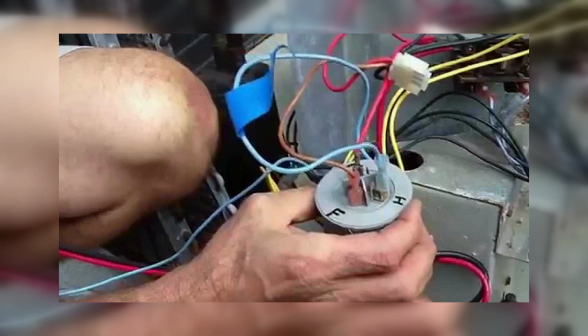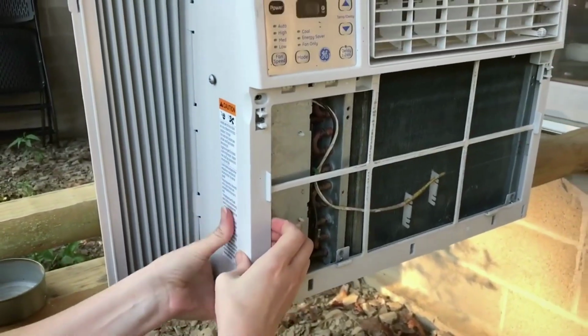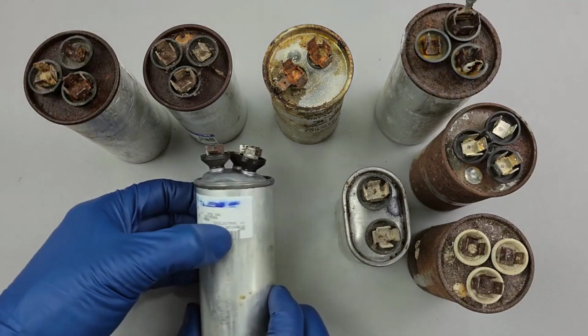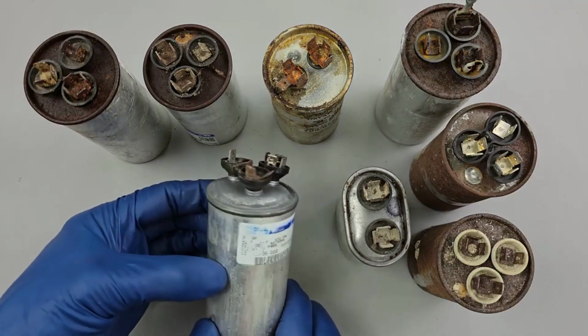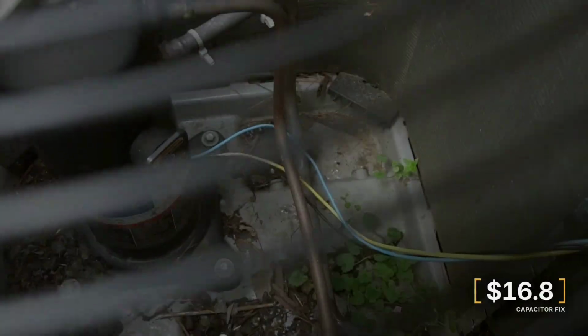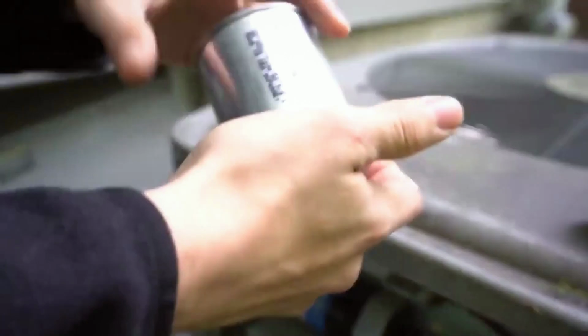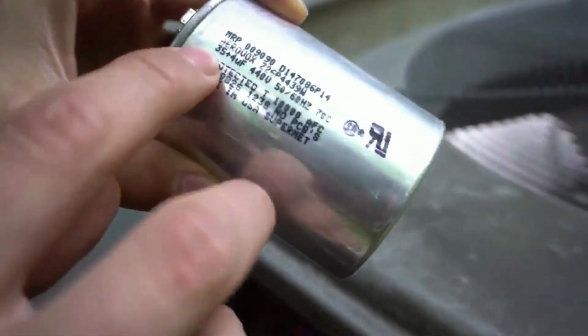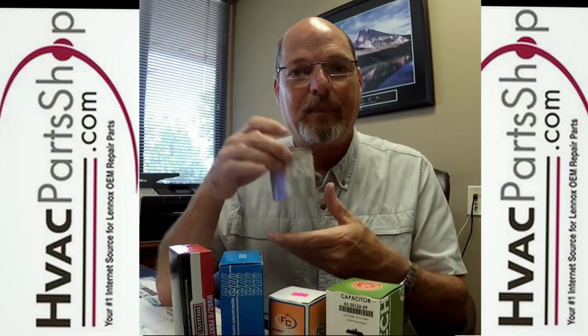Everything was in place. The homeowner just didn't know what everything was building toward until they looked at the label on the old part. Every capacitor carries 3 numbers that must match your system exactly. Get all 3 right, and the repair works. Get one wrong, and you risk motor damage that turns a $30 fix into a much larger problem. These numbers are printed directly on the side of the capacitor you are replacing, but they are non-negotiable.